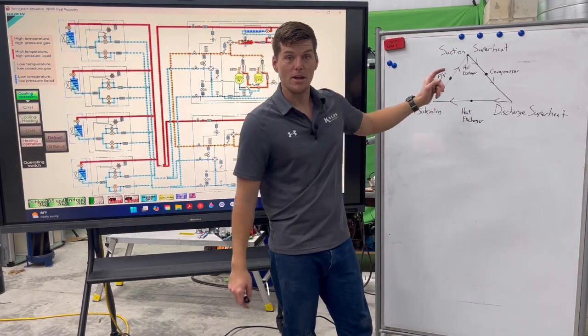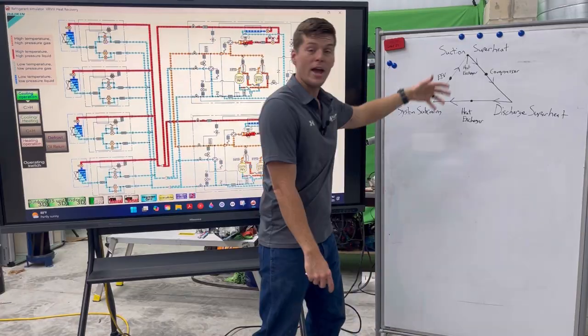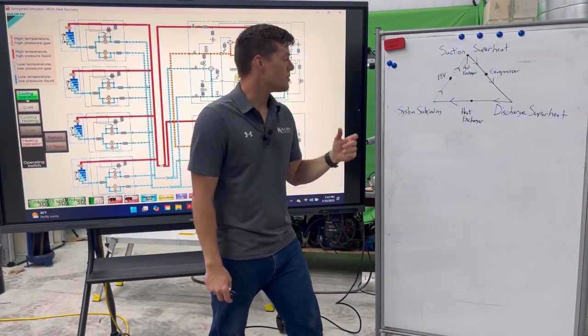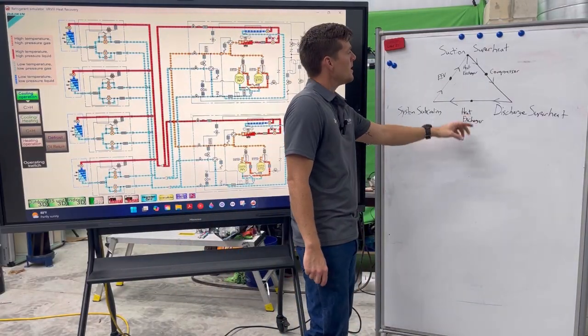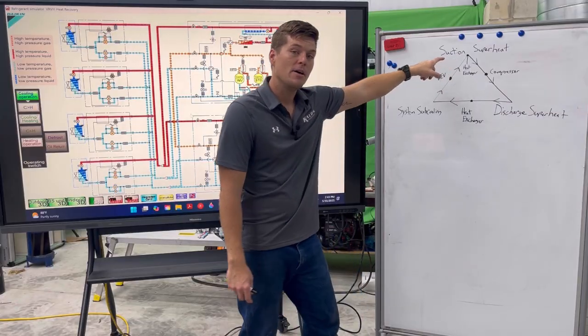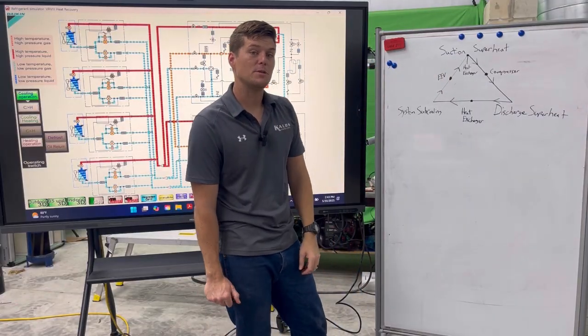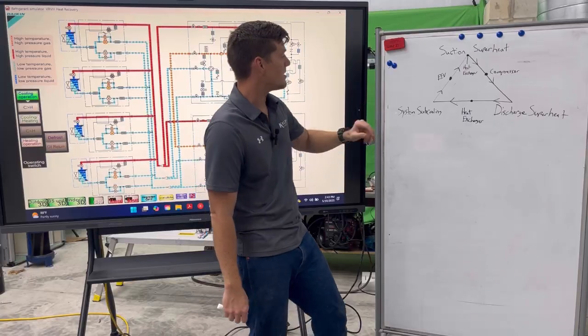So I drew this diagram here, which is basically a triangle, right? Because that is the 3 pillars. They're all connected to each other. You have suction superheat here at the top. The reason I put suction superheat here at the top is because it's usually the first thing that I check when looking at a system.